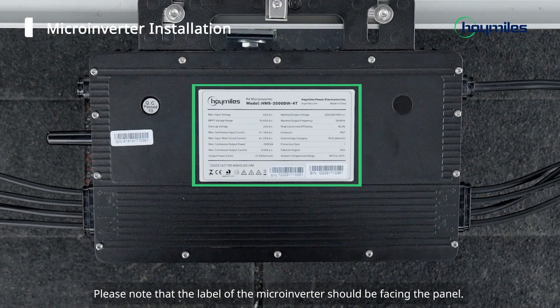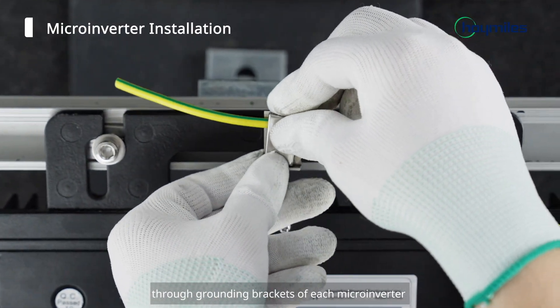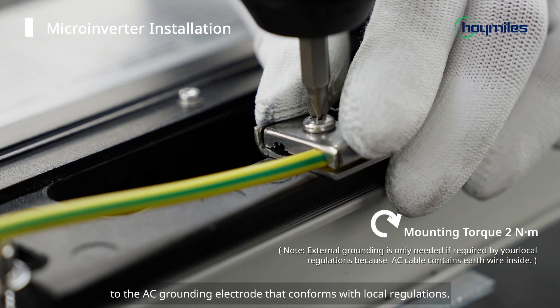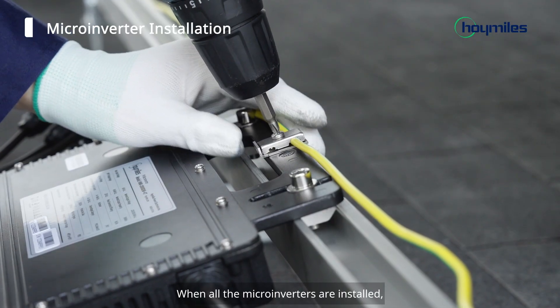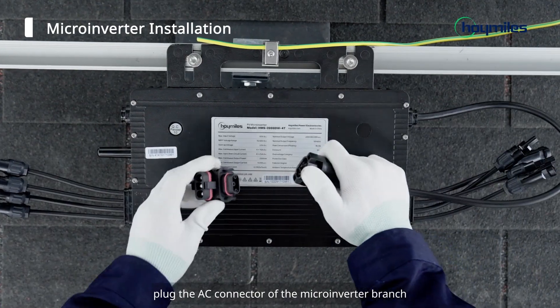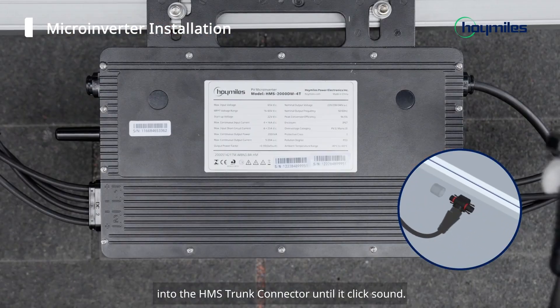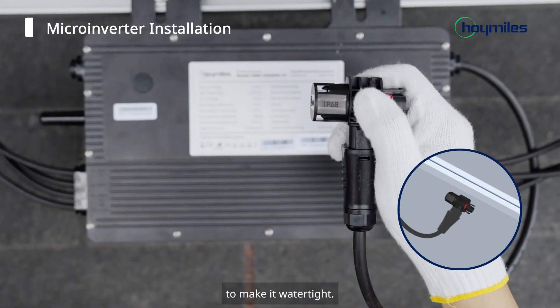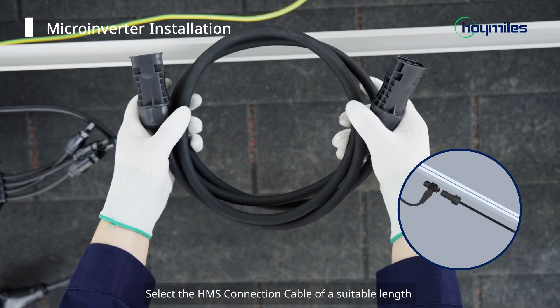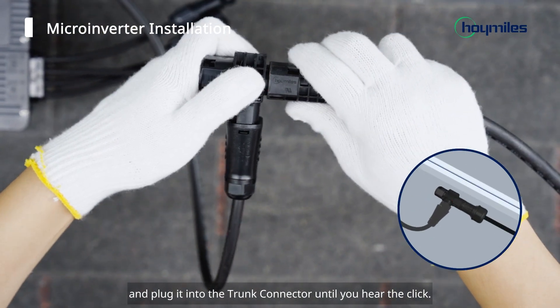Please note that the label of the microinverter should be facing the panel. Then route a continuous grounding cable through grounding brackets of each microinverter to the AC grounding electrode that conforms with local regulations. When all the microinverters are installed, plug the AC connector of the microinverter branch into the HMS trunk connector until you hear a click sound. Then cover the unused port with the HMS sealing cap to make it watertight. Select the HMS connection cable of a suitable length and plug it into the trunk connector until you hear the click.